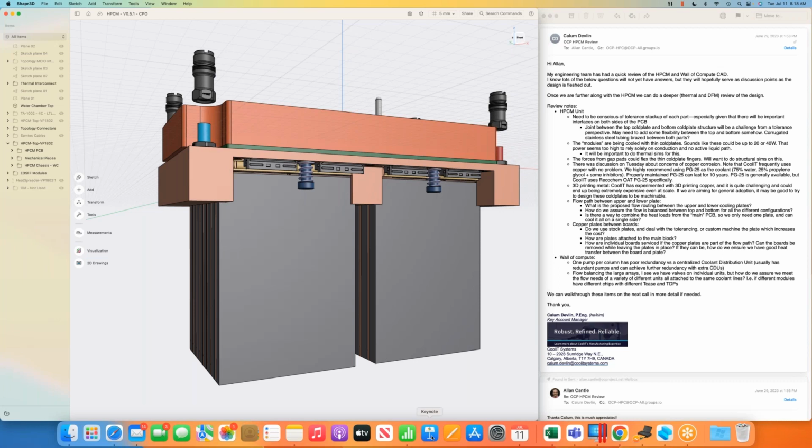So these would be mounted vertically on the wall. You wouldn't put them in immersion because they'd be very shallow. It's all about serviceability. We want a gantry robot to be able to service this as well. It would be entirely a closed data center with no human involvement, ideally.